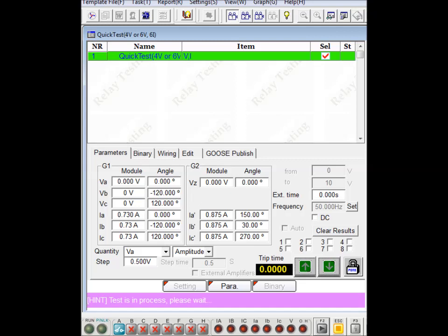First we have to give the stable current. Since the rating is 50 MVA, the HV voltage is 132 kV and the LV voltage is 33 kV, the HV full load current is 218 ampere, that is, the secondary current is 0.73 on full load, as the CT ratio is 300/1.